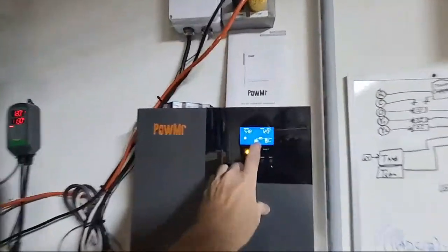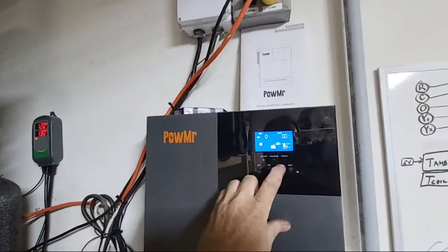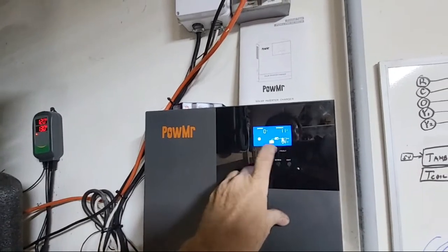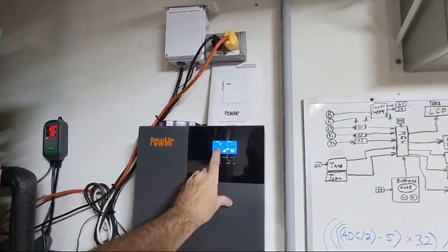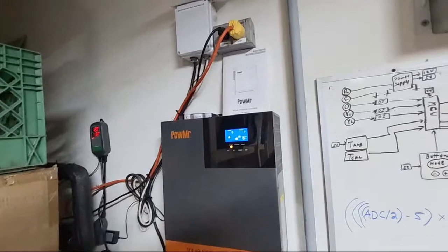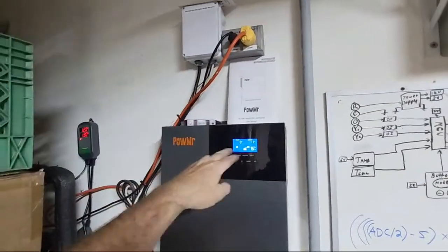So it's running all on batteries now. You can see the battery amps out are 11. We've seen it go to 40, 50 amps to charge, and then it throttles down. Once it gets up to 57, it's all down to just a couple amps. So this thing's working perfectly.